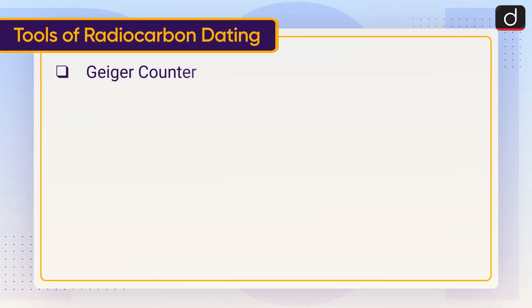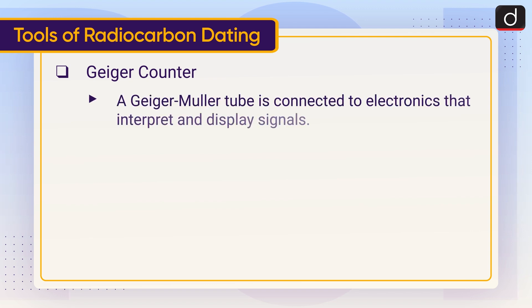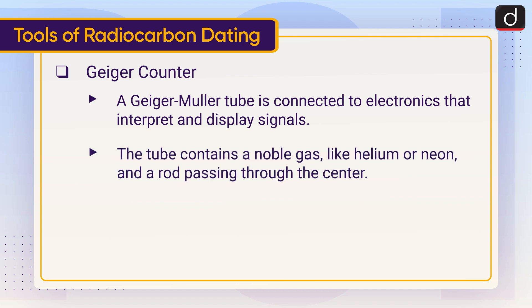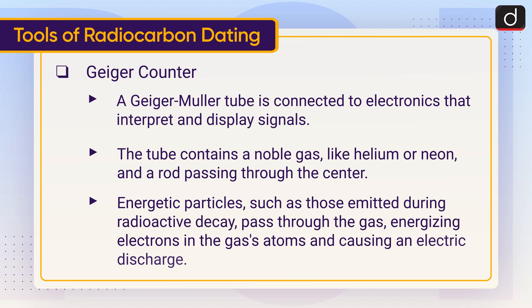Geiger counter: A Geiger-Müller tube is connected to electronics that interpret and display signals. The tube contains a noble gas like helium or neon, and a rod passing through the center. Energetic particles, such as those emitted during radioactive decay, pass through the gas, energizing electrons in the gas atoms and causing an electric discharge.